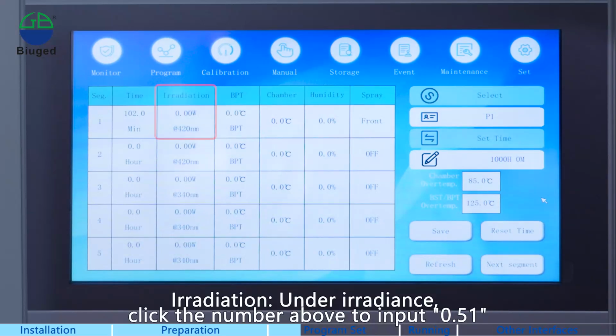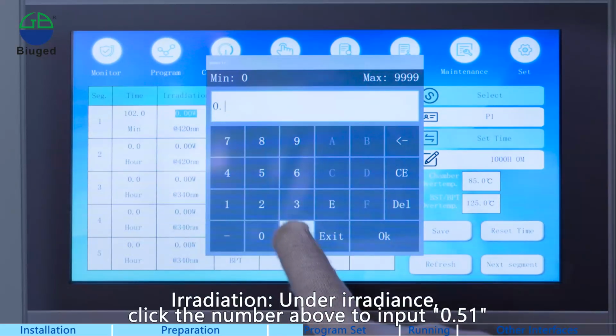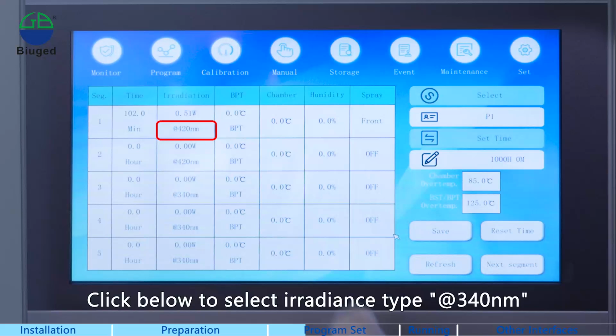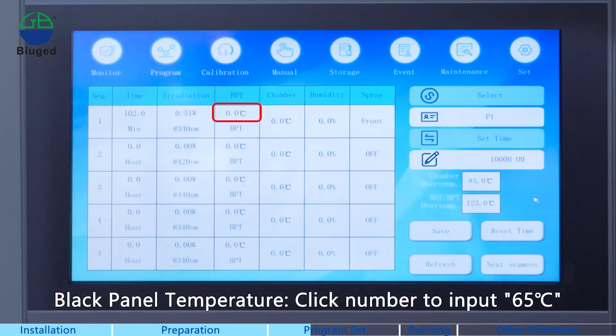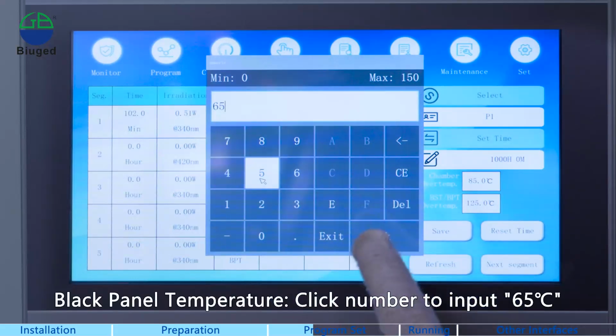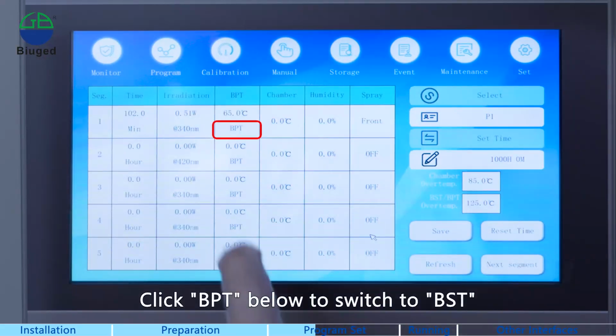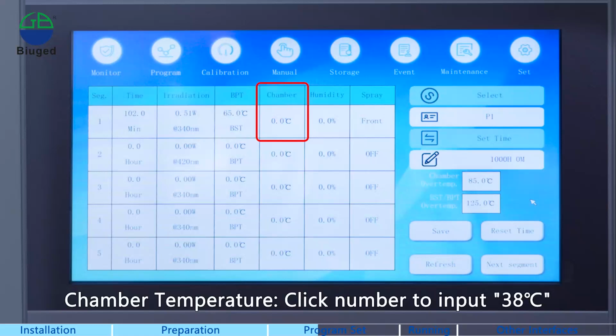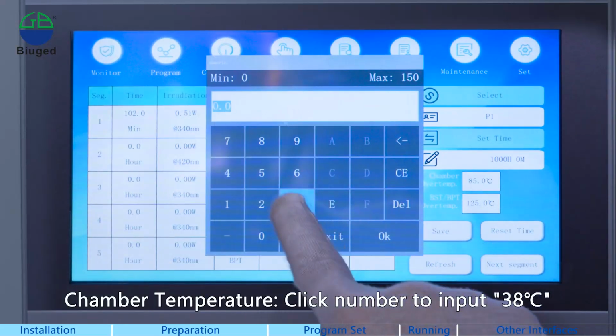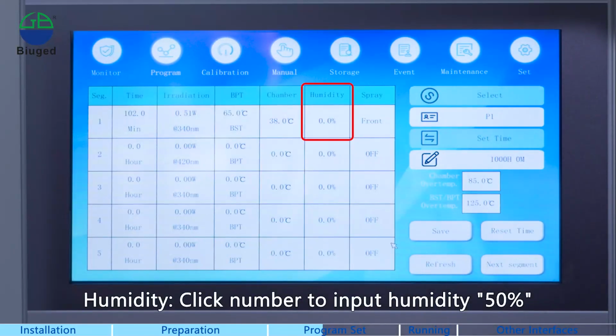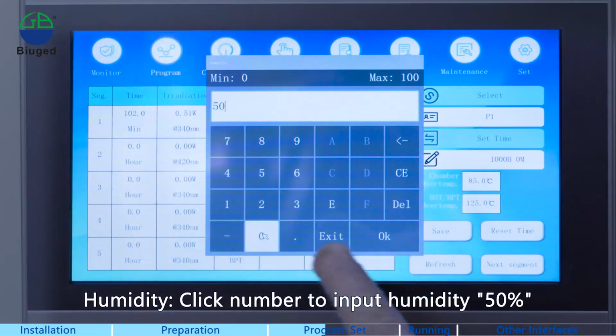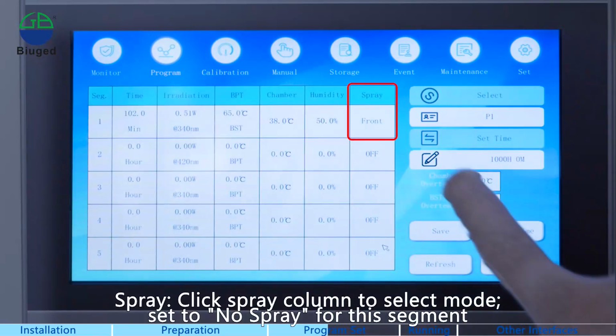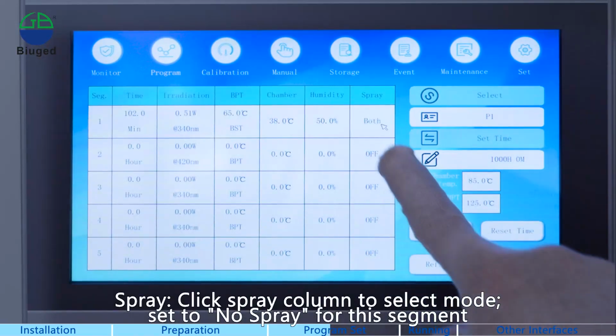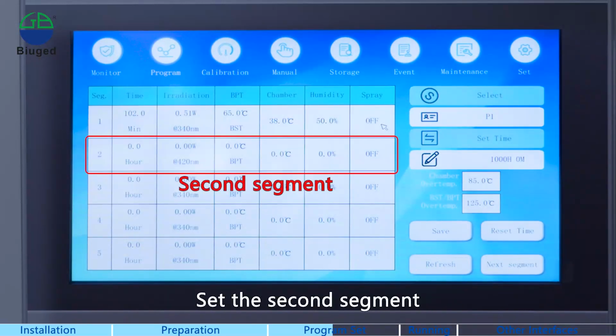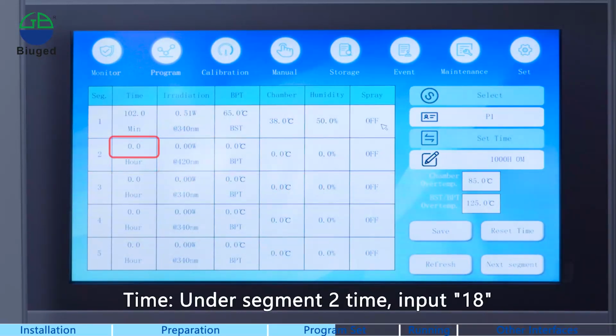Irradiance, under Irradiance, click the number above to input 0.51. Click below to select irradiance type at 340 nm. Black panel temperature, click number to input 65 degrees Celsius. Click black panel below to switch to black standard. Chamber temperature, click number to input 38 degrees Celsius. Humidity, click number to input humidity 50%. Spray, click spray column to select mode, set to no spray for this segment. Set the second segment. Time, under segment 2 time, input 18.